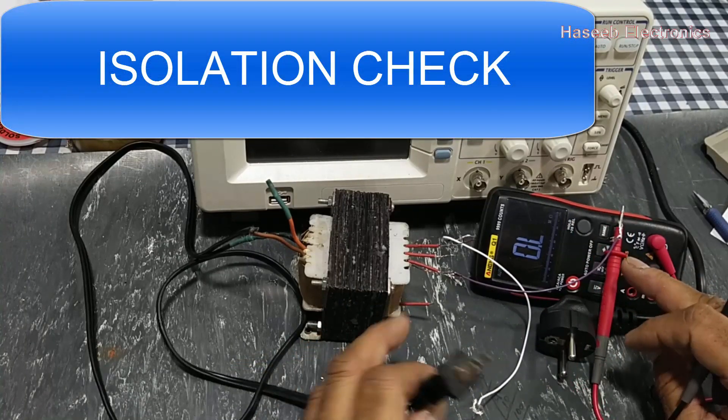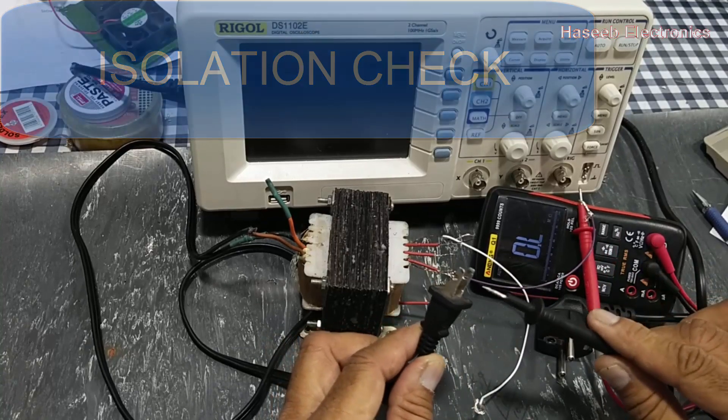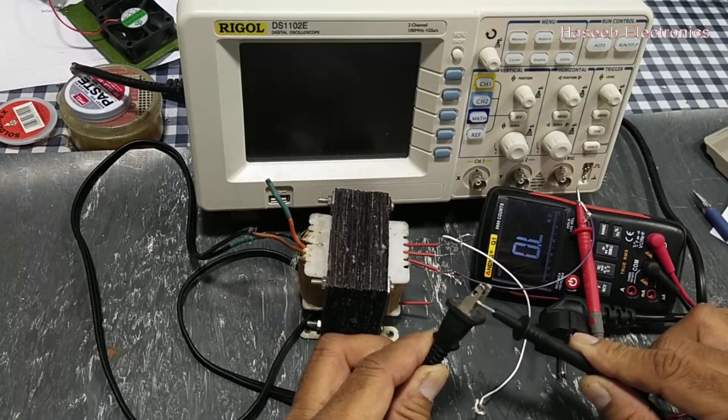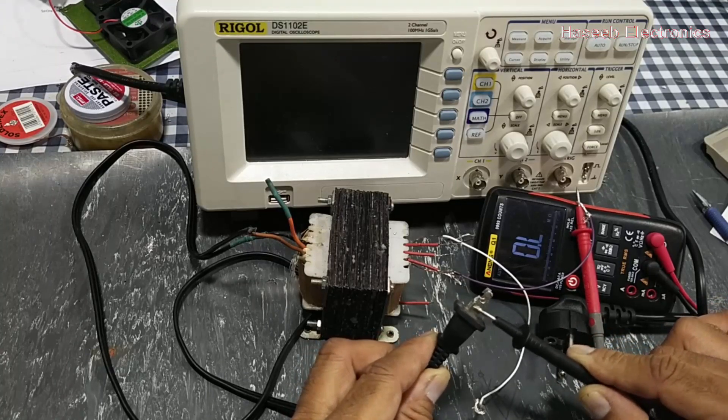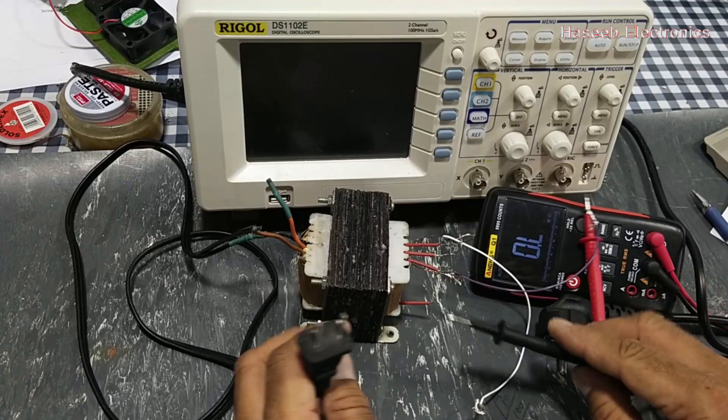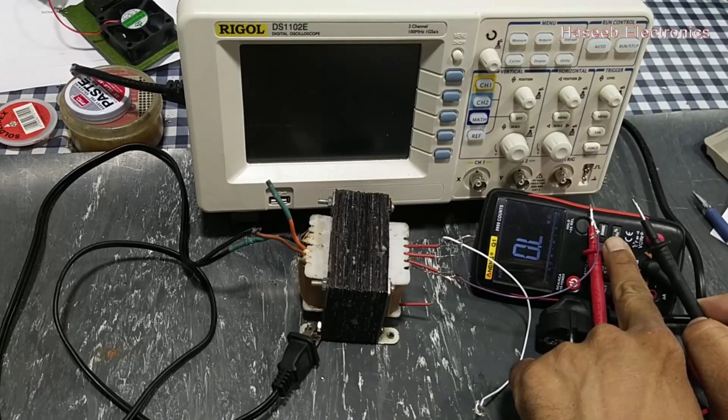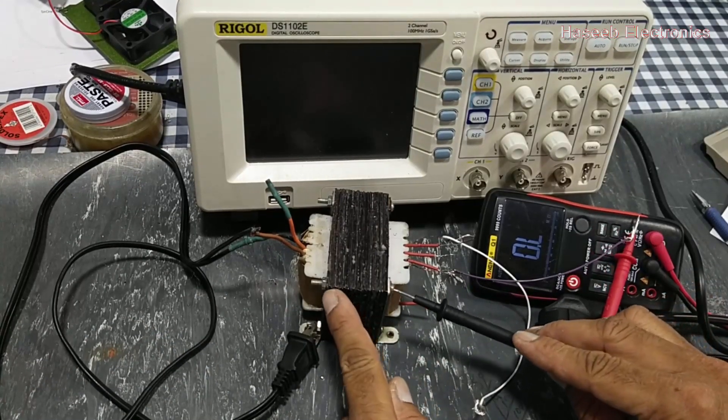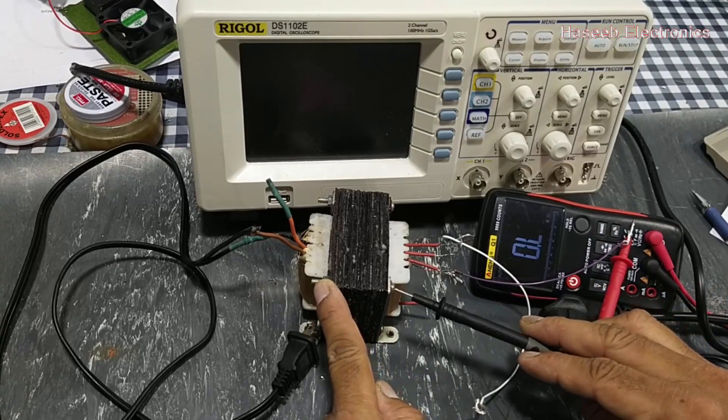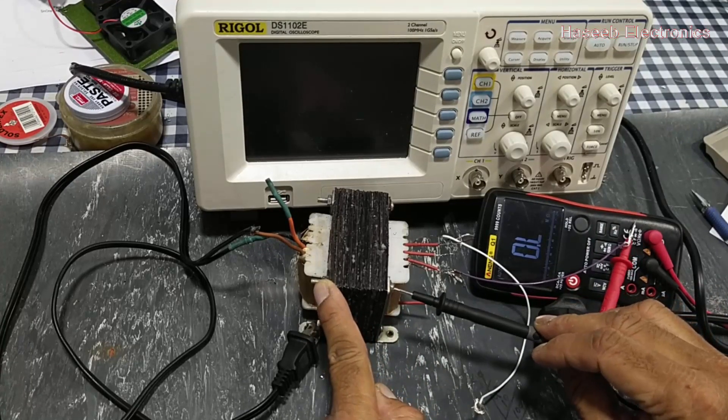Now we can connect one test lead to one end of the secondary winding and the second test lead to one side of the primary winding. We don't have any resistance here. It should not have any resistance. Now one lead is connected here, second lead connected to the chassis, the core, so it is open. That's good. Winding should not have any connection with the core.